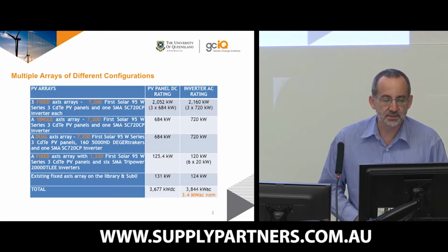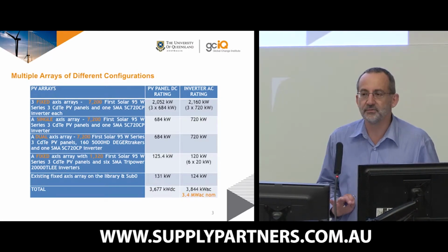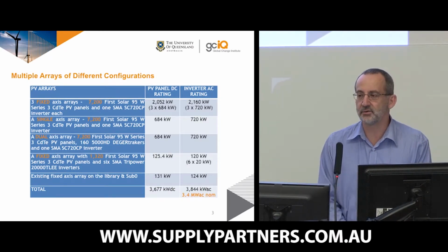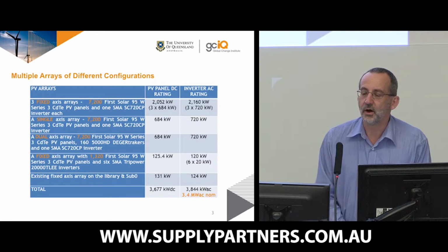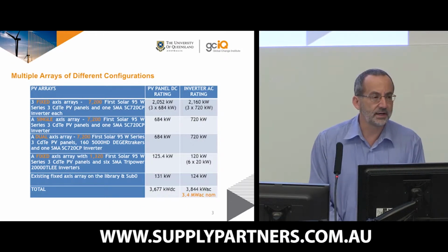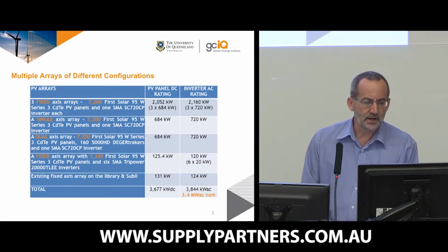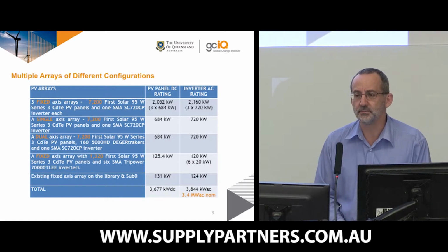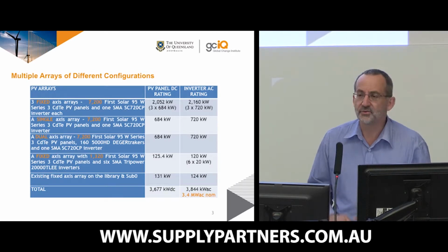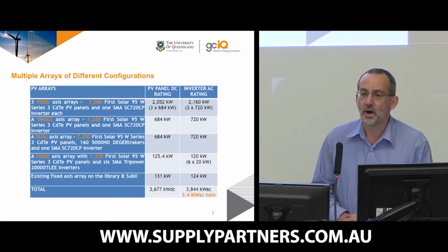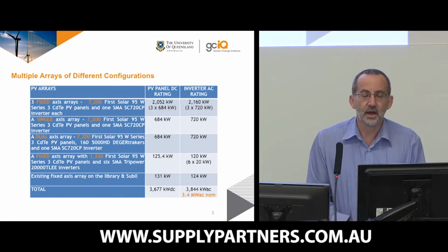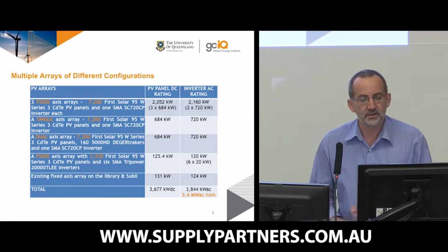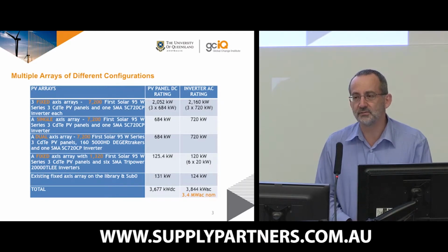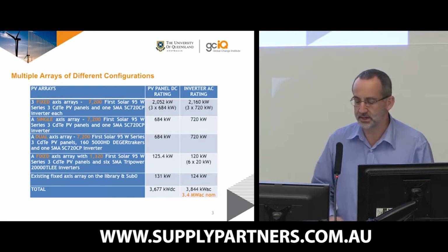The size of the system, and I won't go into all the details: we've got 5 large subarrays, each on 720 kVA SMA inverters. There are 7,200 First Solar panels on each of those. 3 of those arrays are fixed, 1 is a single-axis array, and 1 is a dual-axis array. There is also another smaller 125 kilowatt array, which is still to be connected.